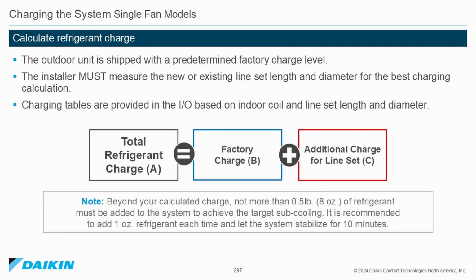Note, beyond your calculated charge, not more than 0.5 pounds or 8 ounces of refrigerant must be added to the system to achieve the target subcooling. It is recommended that you add 1 ounce of refrigerant each time and let the system stabilize for 10 minutes.